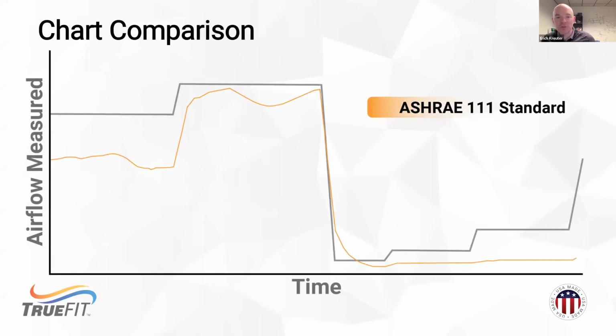So normal operation first. The black line here is damper position. So we start, left to right, with something that's about 2/3 open. And then we close it down to a minimum position in the second half of the chart. The yellow line here is that ASHRAE 111 equation. So again, this is the balancer number in real time. We see a little bit of lag after the damper moves as those temperature sensors acclimate, which is normal and to be expected. That's one reason why we can't just use a temperature measurement out of the box, why we need that characterized airflow performance measurement, because our measurement is instantaneous. And there are times where we don't have delta T in the building, so we need some sort of reference, which is the inclinometer and that performance table.